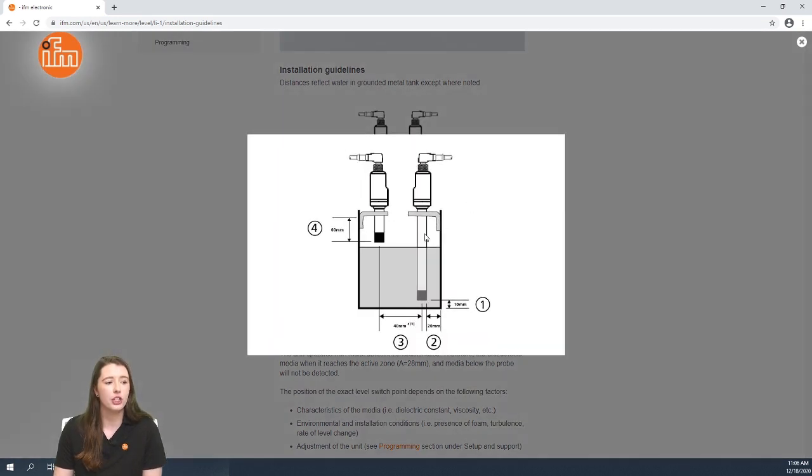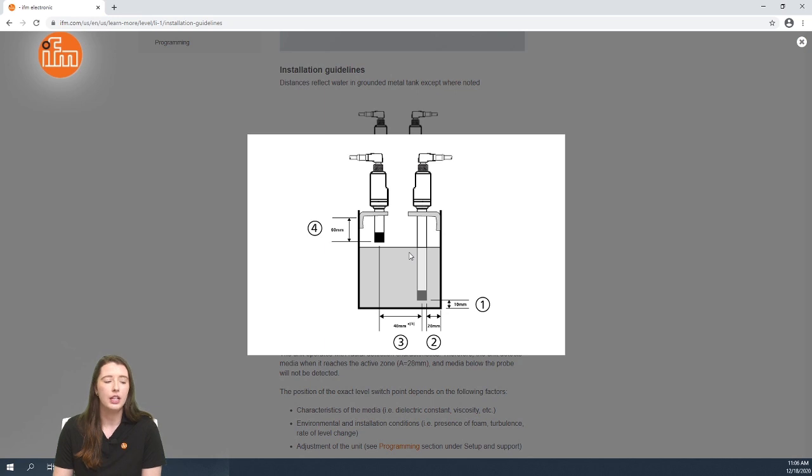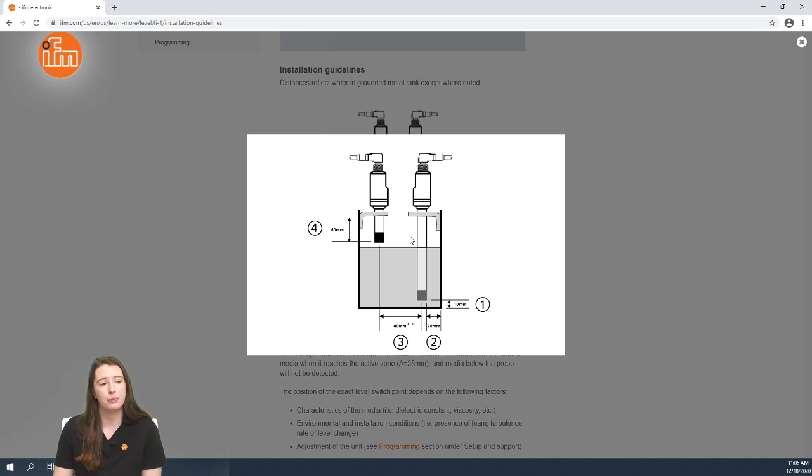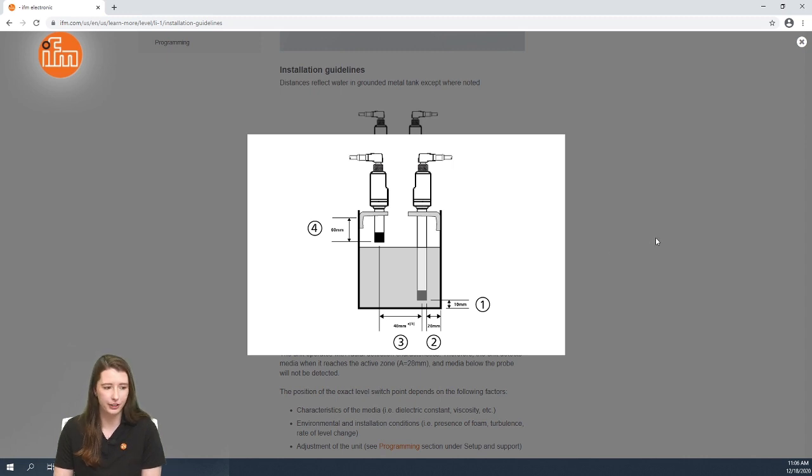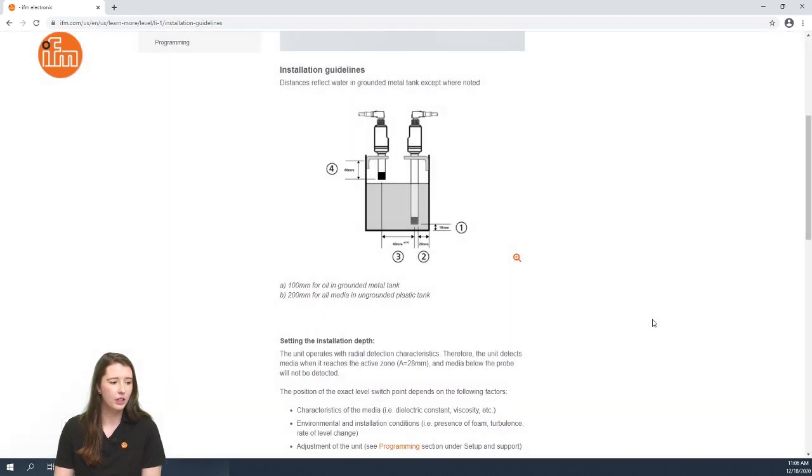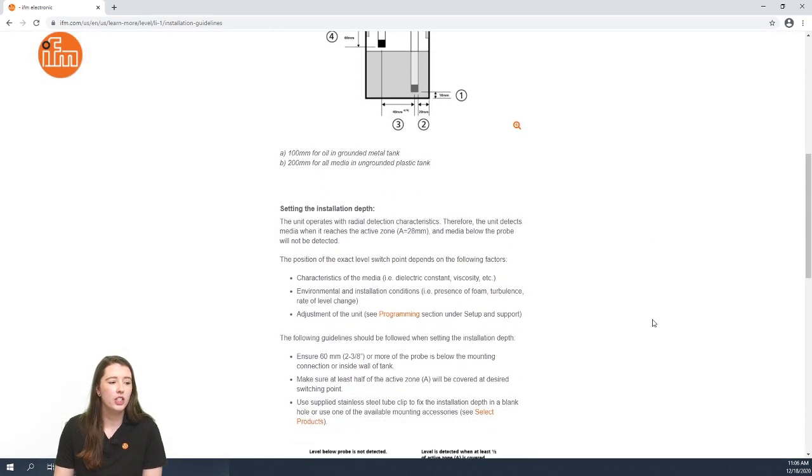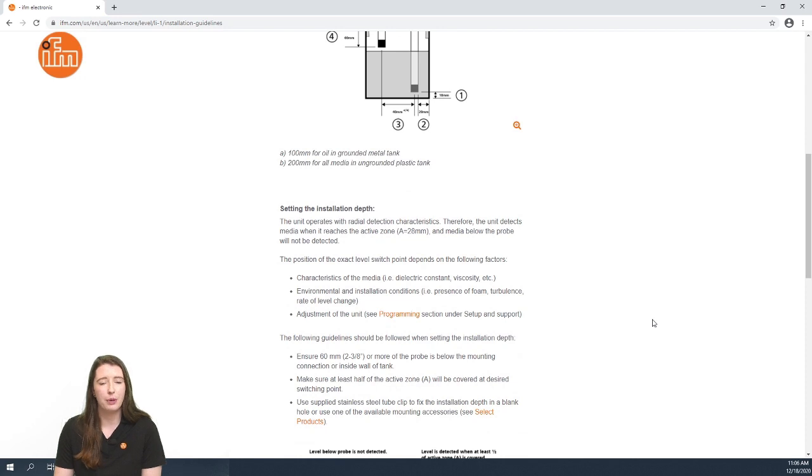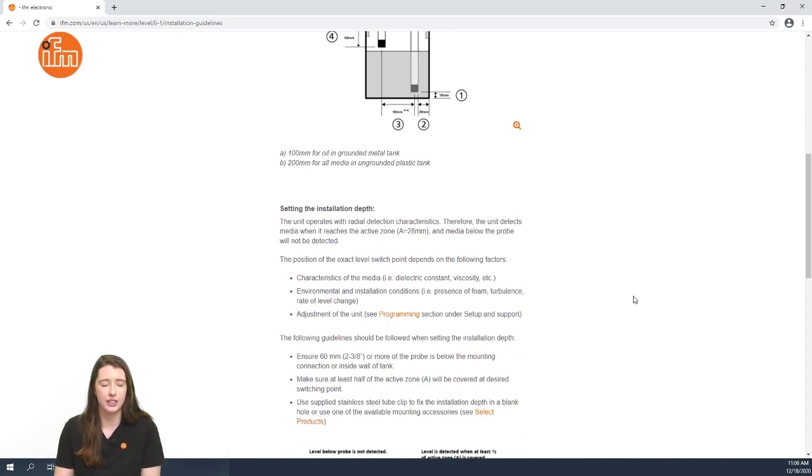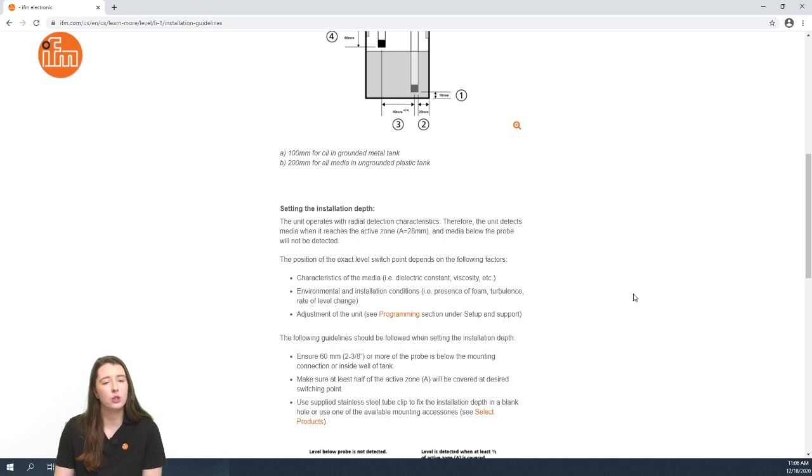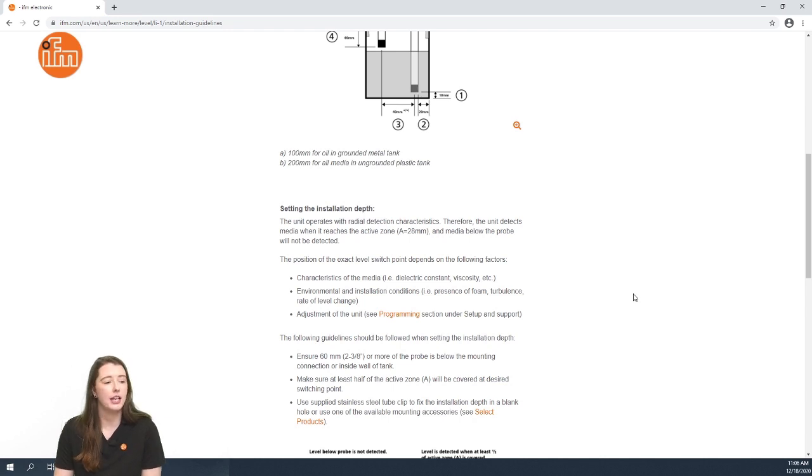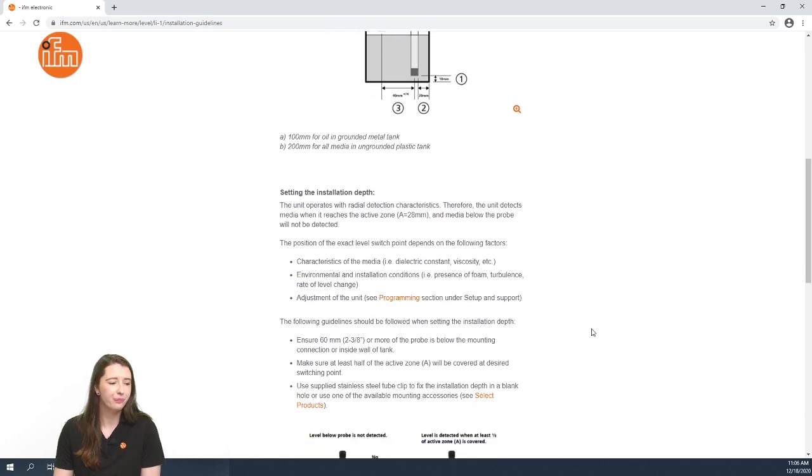These sensors have a 28 millimeter active zone and for the sensor to properly switch, half of the active zone must be covered. The position of the exact level switch point depends on a few other factors such as the characteristics of the media, environmental and installation conditions, and as well as the adjustment of the unit which I will show you in a separate video.